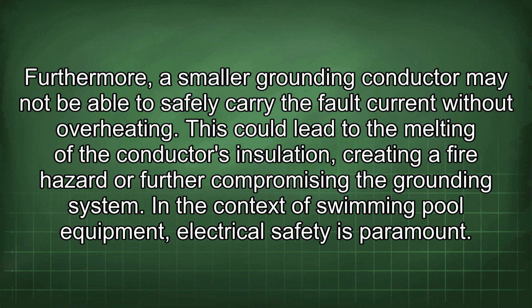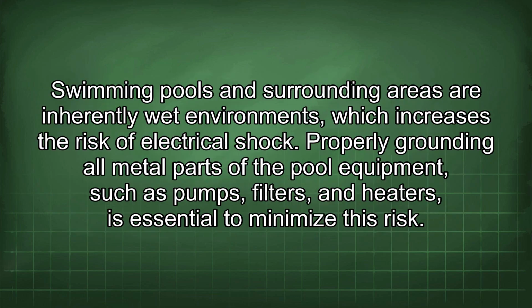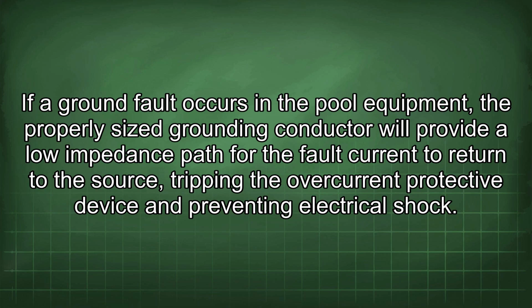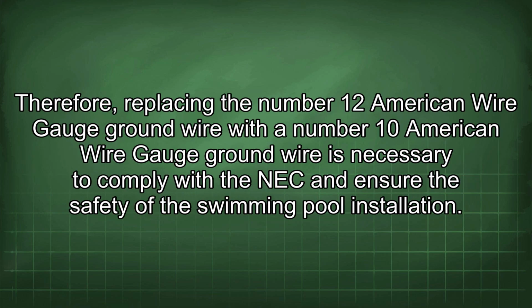In the context of swimming pool equipment, electrical safety is paramount. Swimming pools and surrounding areas are inherently wet environments, which increases the risk of electrical shock. Properly grounding all metal parts of the pool equipment, such as pumps, filters, and heaters, is essential to minimize this risk. If a ground fault occurs in the pool equipment, the properly sized grounding conductor will provide a low impedance path for the fault current to return to the source, tripping the overcurrent protective device and preventing electrical shock. Therefore, replacing the number 12 American wire gauge ground wire with a number 10 American wire gauge ground wire is necessary to comply with the NEC and ensure the safety of the swimming pool installation.